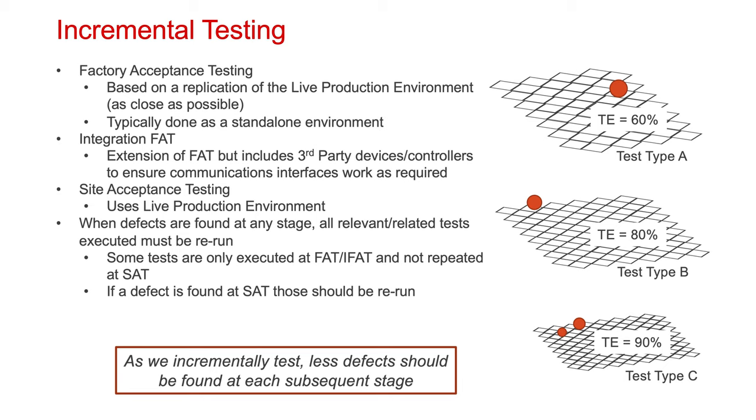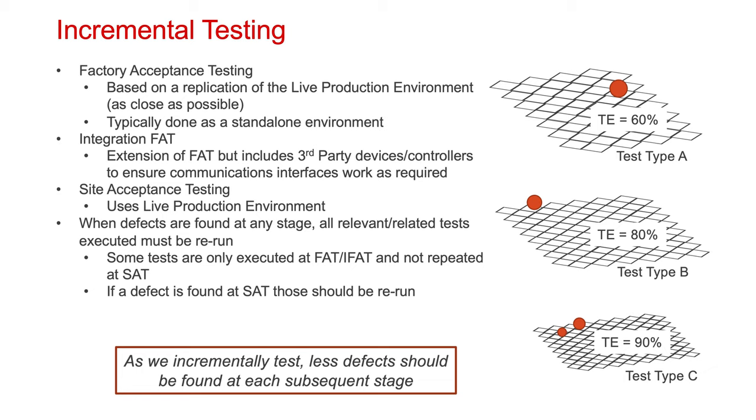The mapping of the data points, the polarity, and the data formats are very important to make sure that they match, align, and are tested thoroughly. A site acceptance test is ultimately the end goal, whereby you are at site — sometimes perhaps not physically — but your implementation has been put onto the real-world system, at which point you are using your live production environment. Whenever defects are found at any stage, all the relevant and related tests need to be re-run and re-executed, because we don't know that the fix applied hasn't detrimentally impacted other associated logic or components. This applies at the FAT and integration FAT stage as much as at the SAT stage. If we're doing our tests thoroughly as we incrementally test during the engineering design process, there should be fewer defects found at each subsequent stage. If there are more defects being found, I'd suggest a problem with test effectiveness and test coverage.